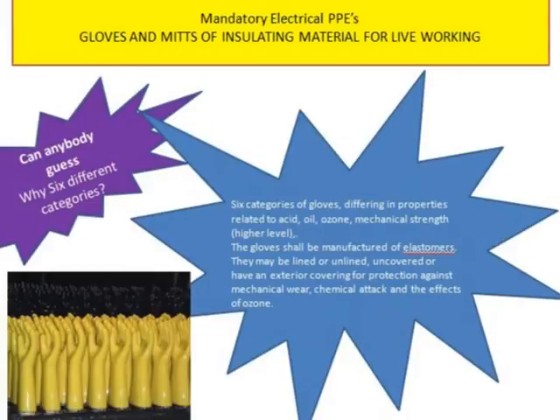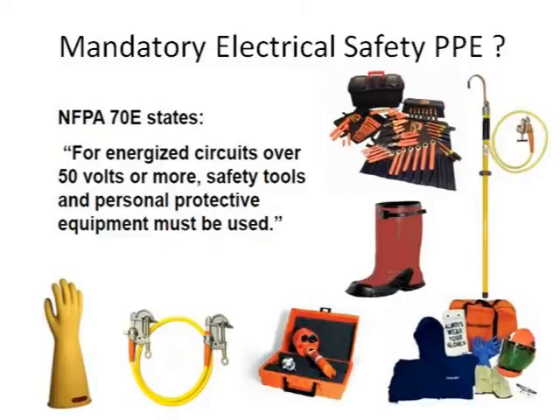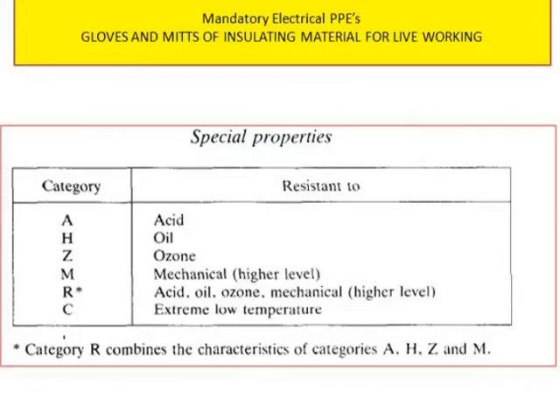When should you use these PPEs? NFPA 70E states that for energized circuits of 50 volts or more, electrical tools and personal protective equipment must be used in combination. This applies to class 0, 1, 2, and 3.